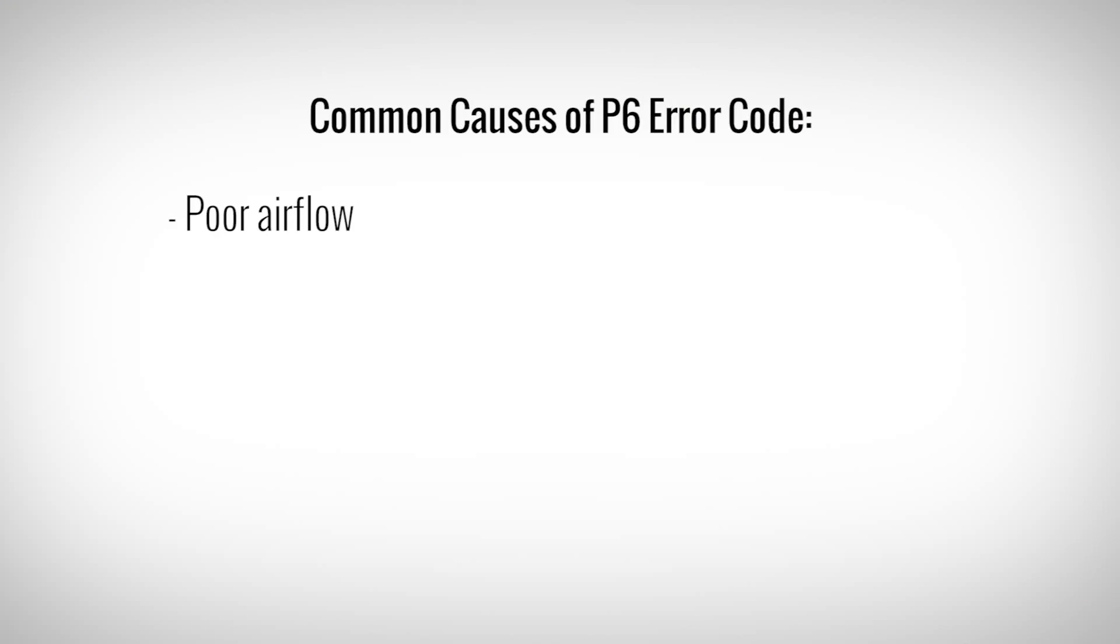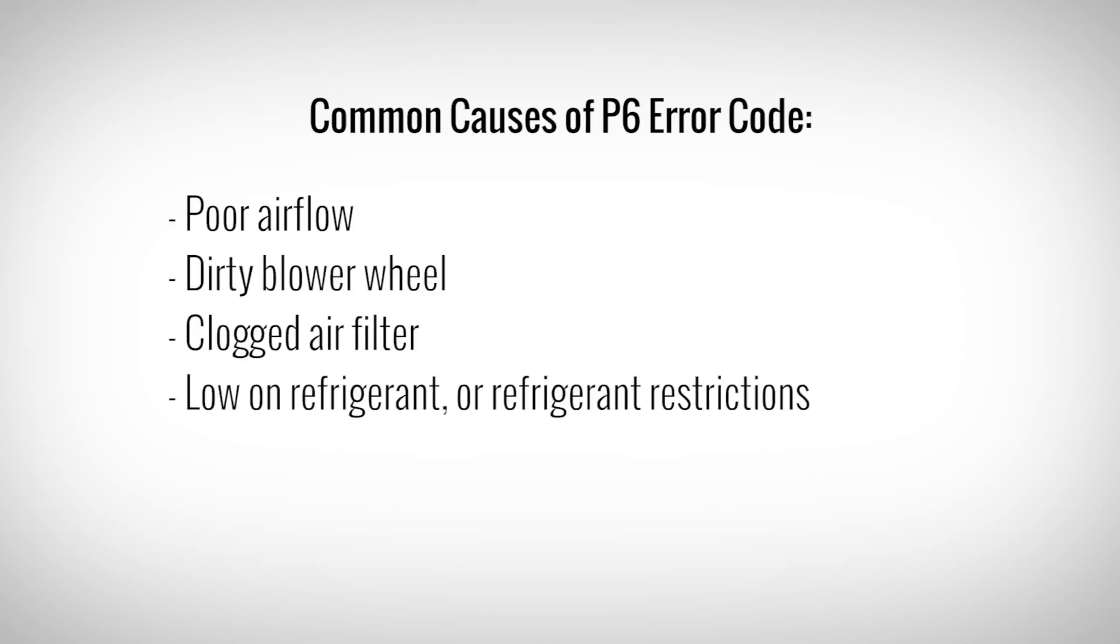There are some common culprits that usually end up causing this error code. Look for items such as poor airflow, dirty blower wheel, clogged air filter, low on refrigerant or refrigerant restrictions, or air recirculating through the return.